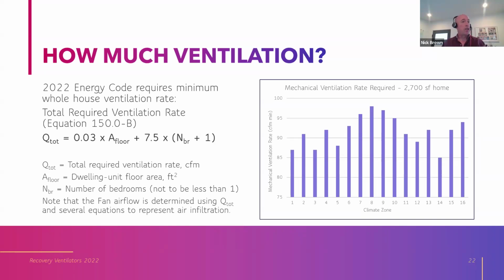So the ASHRAE standard and Title 24, which adopts those ASHRAE standards, calculates the minimum required ventilation rate using this formula. The total ventilation rate is a function of the conditioned floor area and the number of bedrooms. But then why are we showing different minimum CFM for different climate zones, you might wonder? There's no climate zones in that equation.